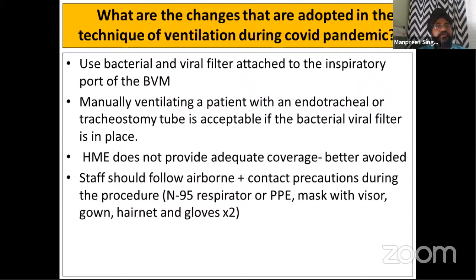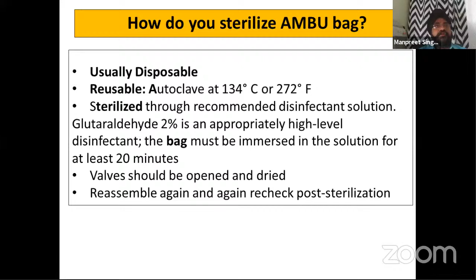So how to sterilize the Ambu bag now? Usually it is disposable, sometimes we have the reusable ones, and autoclave at 134 degrees is the best one. Otherwise you can sterilize the Ambu bag with 2% glutaraldehyde, an appropriately high level disinfectant, and it should be kept in the glutaraldehyde for 20 minutes. Then only it is sterilized. So valves should be opened. Remember this, the valve should be opened and dried completely before reassembling them after the sterilization. And before sterilization, you have to open the valves, otherwise it is not completely sterilized. So reassemble again, and do the pre-use check of all the valves, whether they are rightly fitted or not.